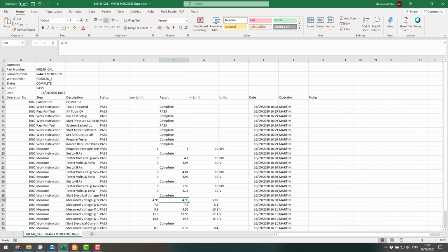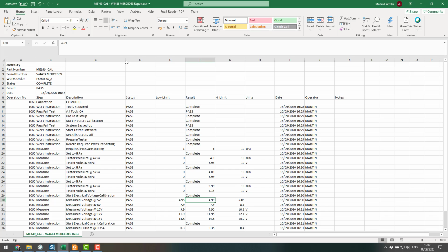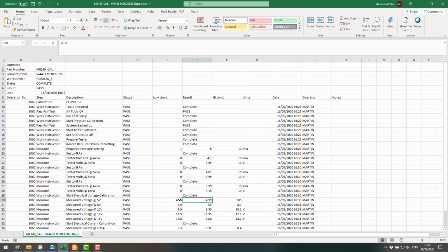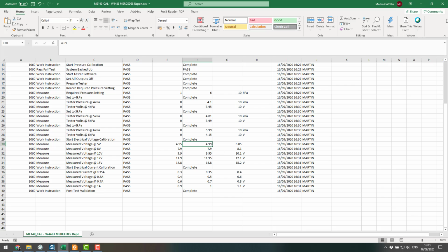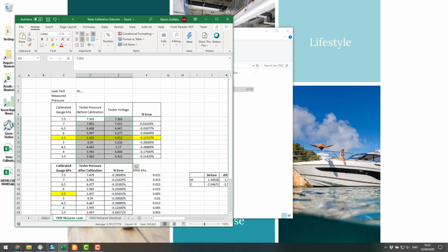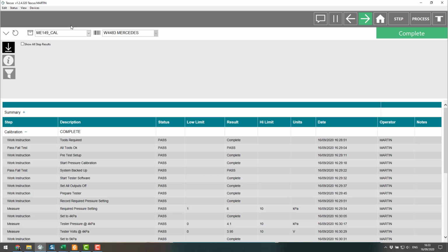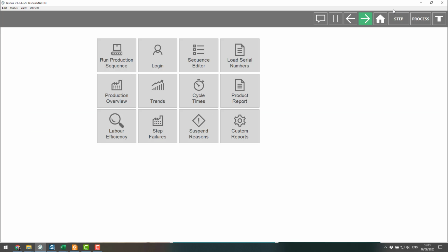And if I did need to make an adjustment, I could even put the formulas in here to calculate what the scaling factor should be if I needed to do an adjustment of any of the calibration. So that's it. I think that's a nice way of switching from a quite clunky paper and Excel based system to a very step-by-step one. You're guided through it and you're guided what data to capture at what point in time.